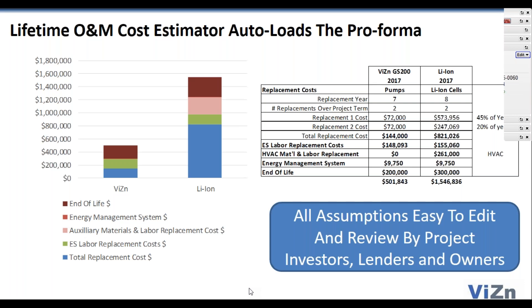For us, the replacements are definitely not on the battery, not on the cell, not on the electrolytes or chemistry. We have to change two pumps — we know they're roughly 10-year assets, but we model it at seven years to be extra conservative. In stark contrast, lithium-ion cells rarely last 10 years. We've modeled them at eight years to find a conservative middle ground. Those cells have to be replaced, which means decommissioning a fully working revenue-generating asset, replacing cells with labor, then recommissioning. The exposure differences between the two platforms are stunning.